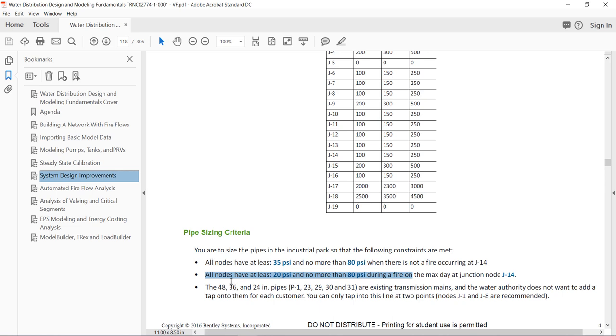The second criteria is to have pressures between 20 and 80 psi in case we have a fire on the maximum day — a fire at junction J14. So we have to consider the maximum day demands scenario and input an additional demand on node J14 to simulate a fire event.